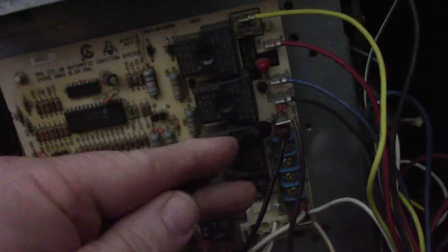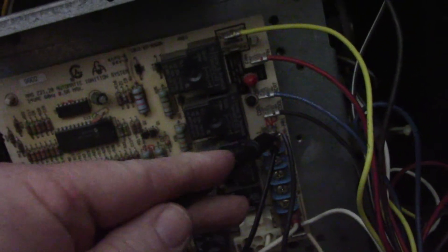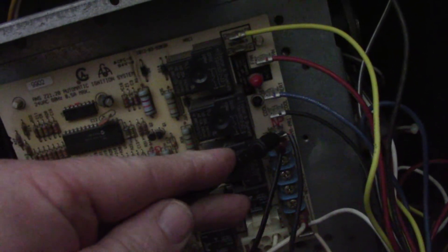You can also take from one line here, the wire here, with it disconnected and go to ground with your meter to see if you have a shorted out transformer to ground.